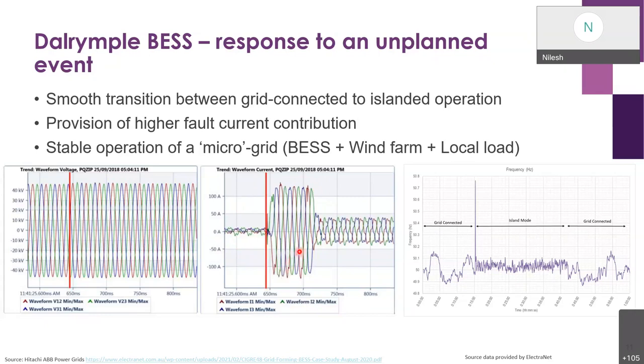It has demonstrated a stable operation of, let's call it a microgrid, with a battery, wind farm, and local load. While it was in island operation, you can see it was controlling the frequency in a very smooth manner. I have only shown the frequency plot here. If you are interested in how the voltage was performing, I suggest you look at the reference, which is available on the screen as well. So this was the response to an islanding event.